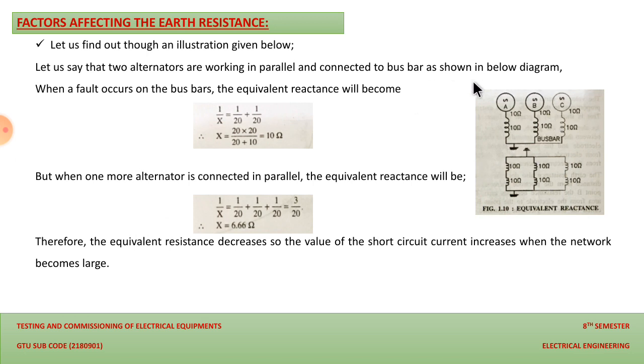So we have discussed through this illustration that if we have two alternators, the reactance is 10 ohm, and if we increase the number of alternators or generators, then the reactance will decrease according to the increase in the number of alternators. As the system becomes large, the short circuit current also increases, and when the network becomes smaller, with fewer pieces of equipment, the short circuit current will be less. This is how we can explain the change of reactance with the size of the system. Hence the earth resistance should be as low as possible for a large system. This is how we can discuss the factors which are affecting the earth resistance.